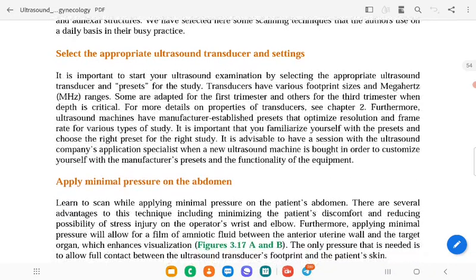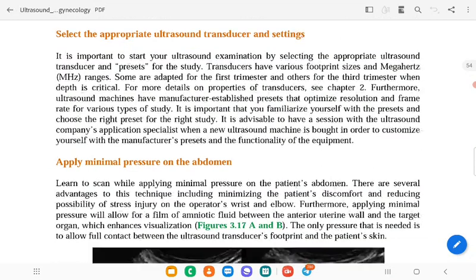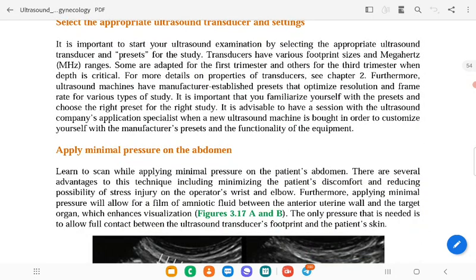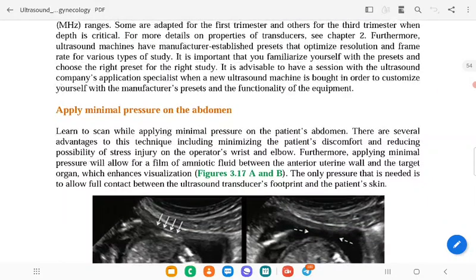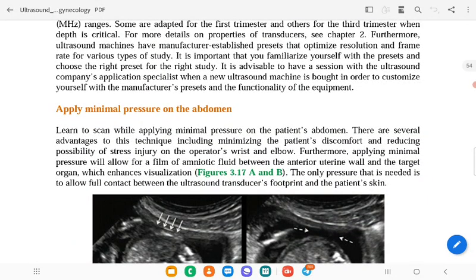Furthermore, the ultrasound machines have manufacturer-established presets that optimize resolution and frame rate for various types of study. It is important that you familiarize yourself with presets and choose the right preset for the right study. It is advisable to have a session with the ultrasound company application specialist when a new ultrasound machine is bought, in order to customize yourself to the manufacturer presets and the functionality of the equipment.